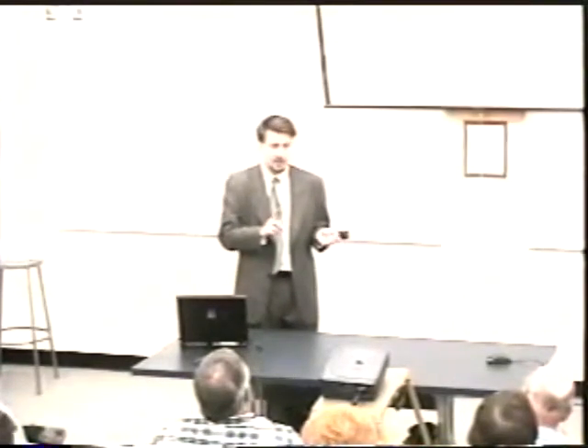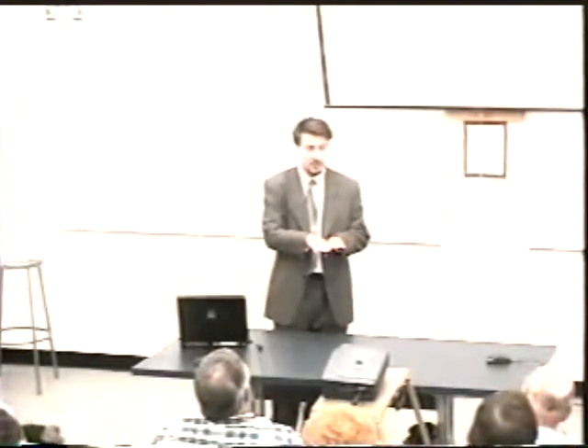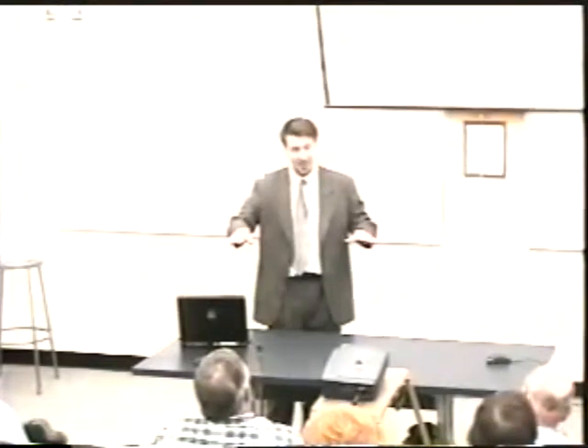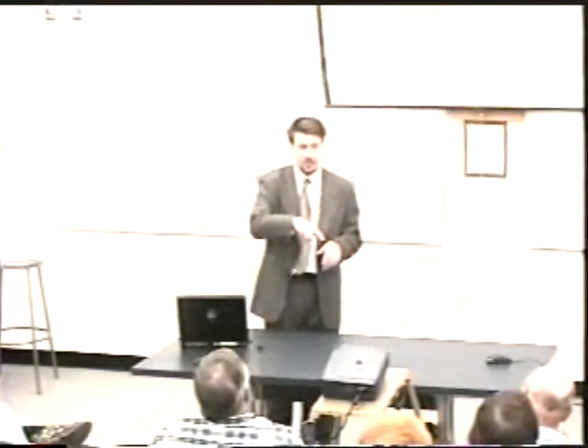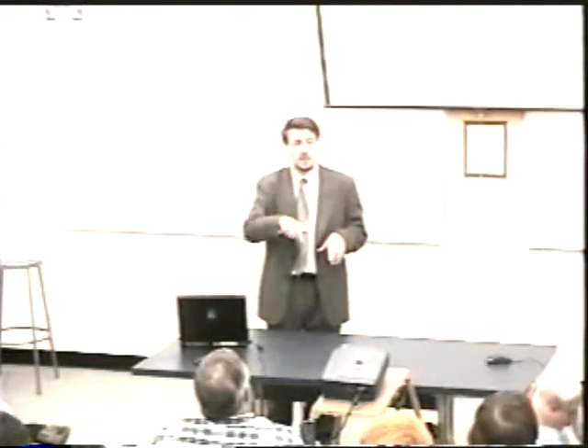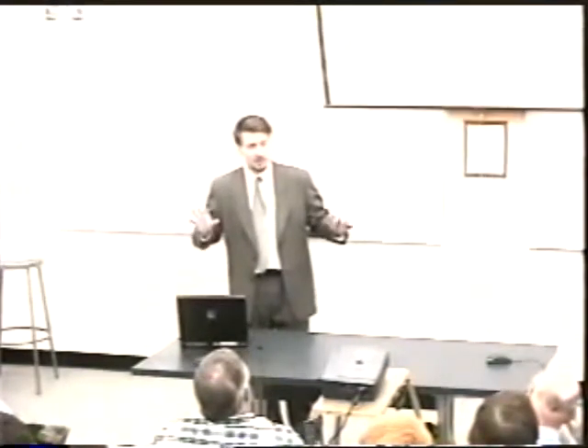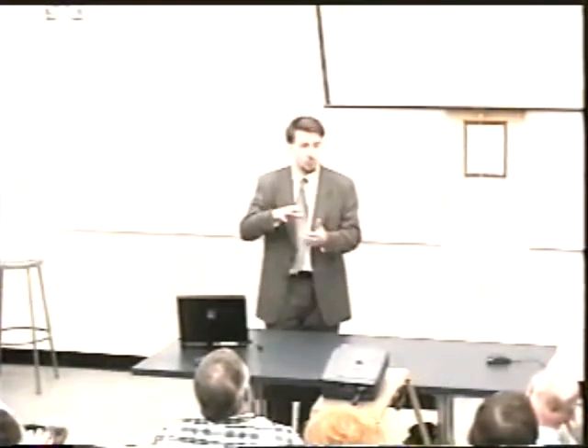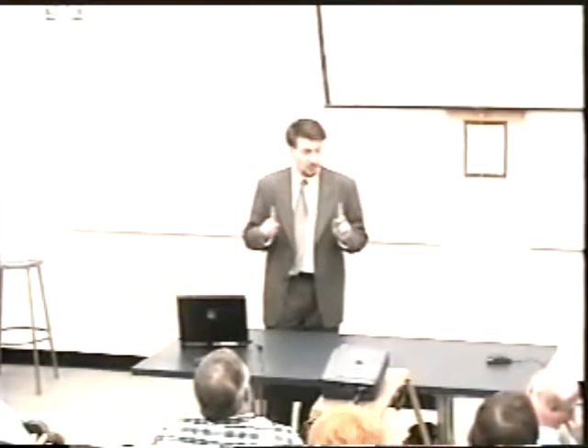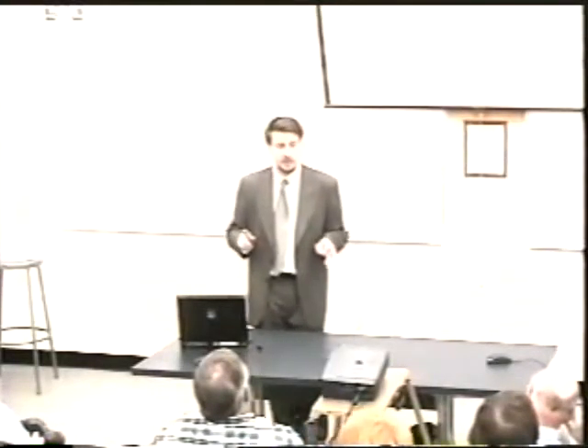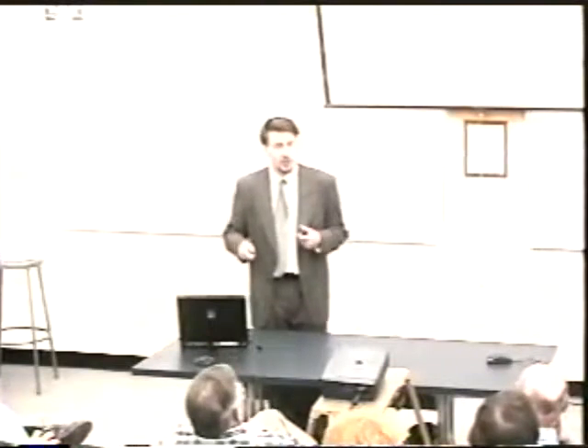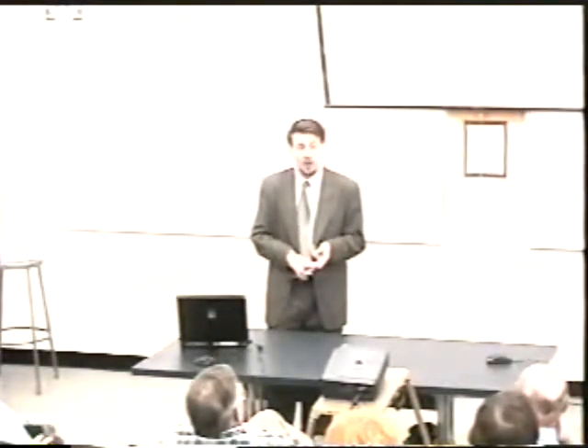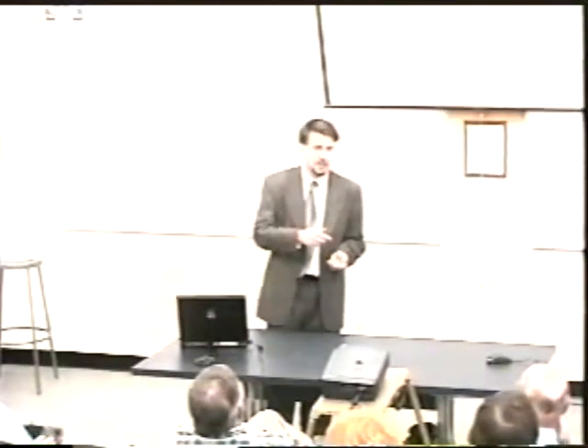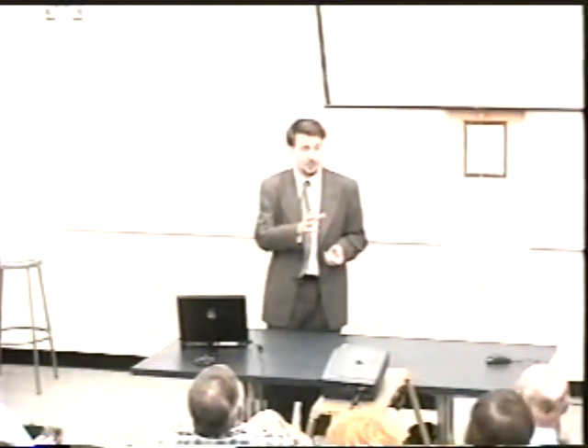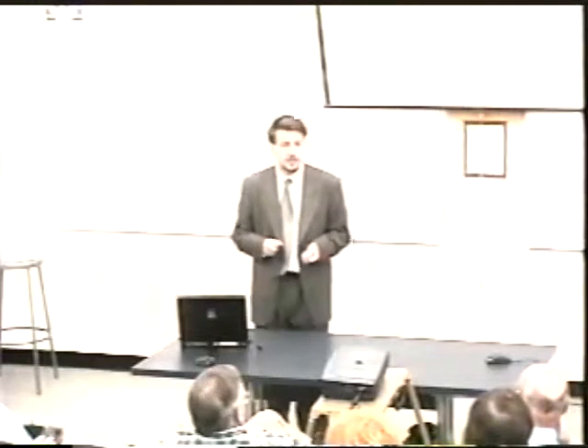The first step is an exact coordinate system. The CT scanner has a special tabletop on it that is indexed to match the tabletop in the treatment room. And both rooms have a laser system to define a coordinate system inside the room. And that's the first line of defense. The second line of defense is on the linear accelerator, we're able to image definitely bone. We can see bone no problem. And many soft tissues, we can see in X-ray images on the accelerator itself. And that's what allows us to fine-tune the position inside the patient.